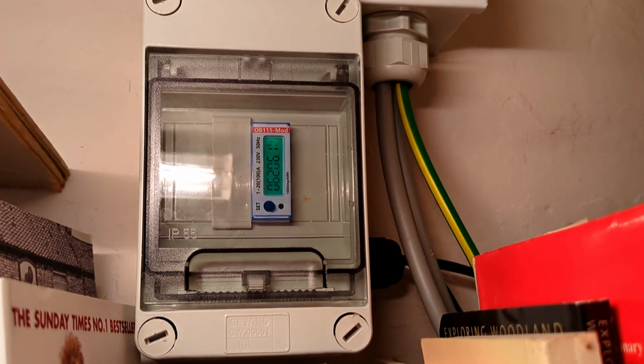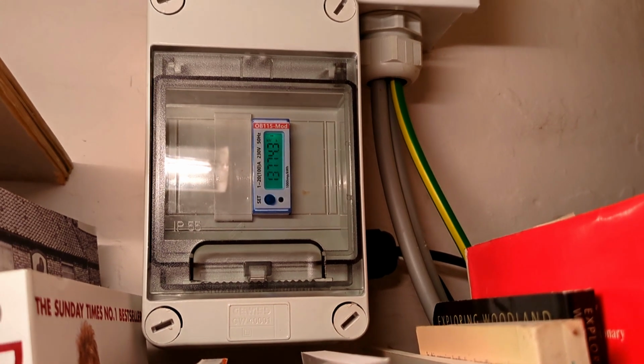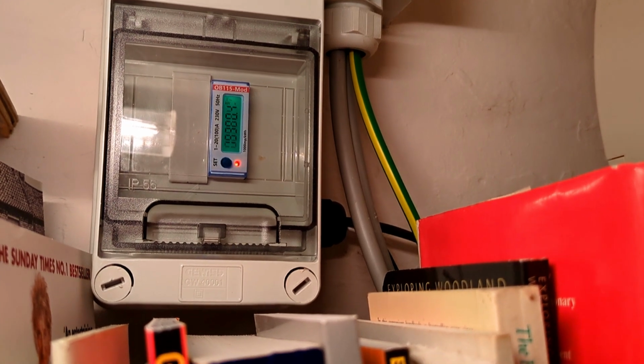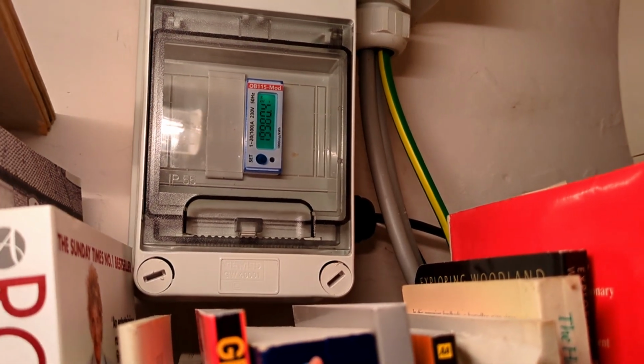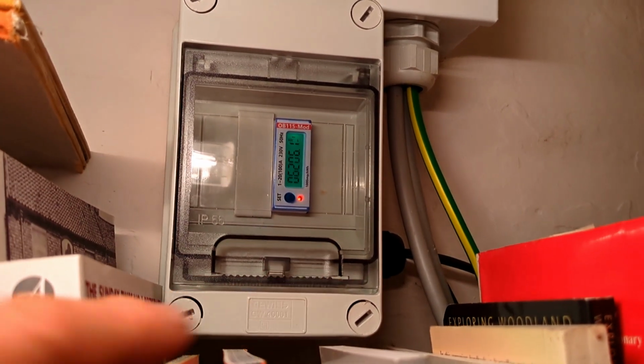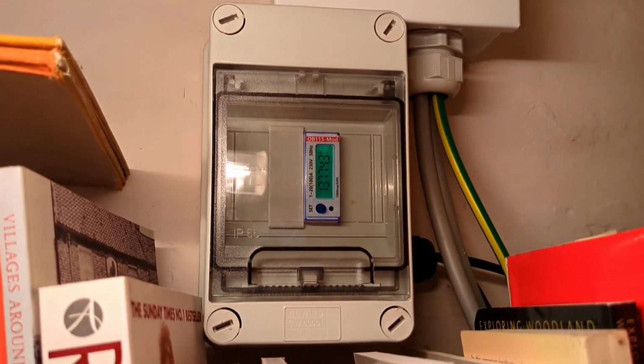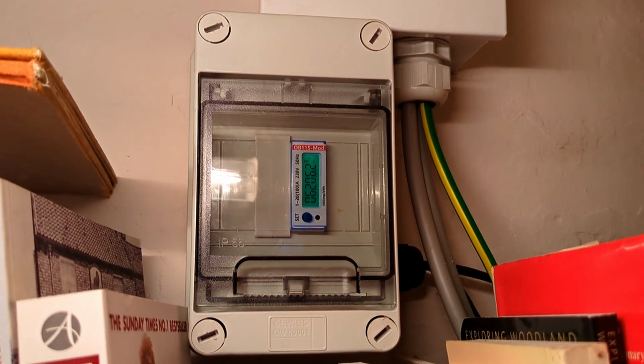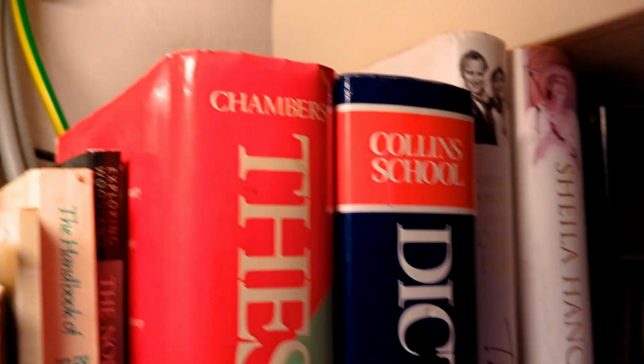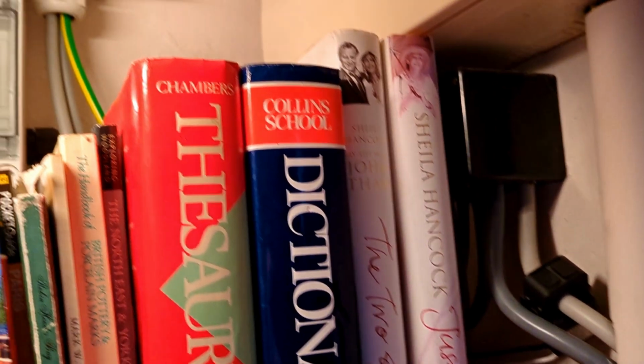And also there's a voltage drop between this in the house and my inverter, which is down the yard. Now it's quite a long cable, although it is a big fat cable. It probably would only drop 0.5 volt between. But you can see how, with all this tied to the grid voltage, if the grid voltage is a bit high, you can add on something like 0.5 volt going down there to the inverter. You can then add on a volt for the inverter to push the power and export it, push it out of the door, down this cable, actually, to the meter and outdoors. So it all kind of adds up.